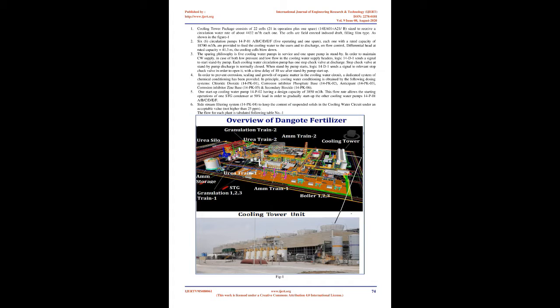Brief description of the cooling tower. The cooling water system is provided mainly for ammonia and urea process cooling requirements and for relevant auxiliary systems, based on evaporative cooling cells of conditioned water routed to the users and then returned to the cooling towers for restoring the proper temperature before being recycled to the users.